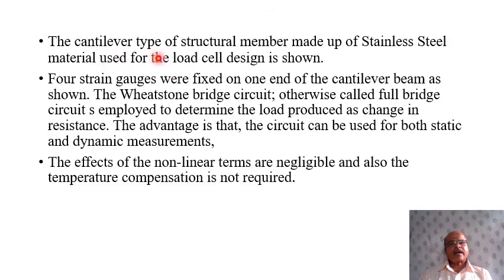The cantilever type of structural member, made up of stainless steel material, is used for the load cell design as shown in the next slide. 4 strain gauges were fixed on one end of the cantilever beam as shown in the next slide. The Wheatstone's bridge circuit, otherwise called a full bridge circuit, is employed to determine the load produced as a change in resistance.